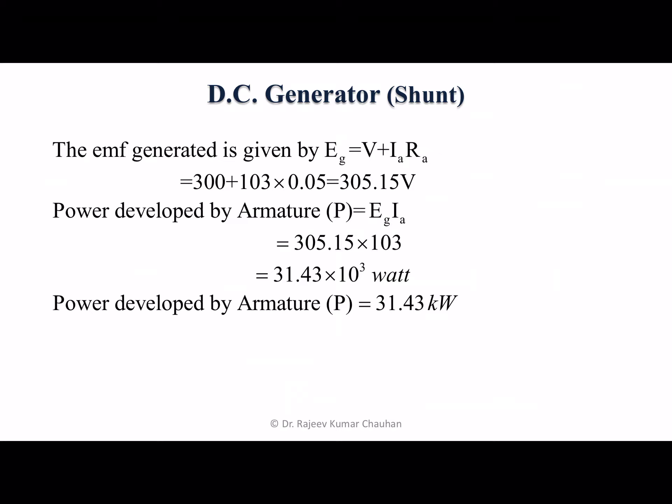The EMF generated is given by Eg equals V plus IA times RA, which is the voltage drop in the armature plus terminal voltage. We know the terminal voltage is 300, armature current is 103, and armature resistance is 0.05, so the EMF equals 305.15 volt.